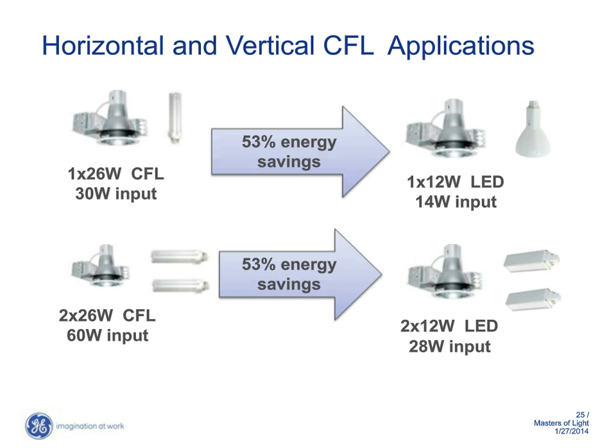What would the numbers look like? First of all, we're going to focus on 4-pin lamps, okay? Specifically 26 watt, maybe even 32 watt, depending on how much light you really need. So let's focus on the 26 watt. I've got a downlight with a single tube installed vertically in that fixture. With the ballast, it's more like 30 watts, okay?